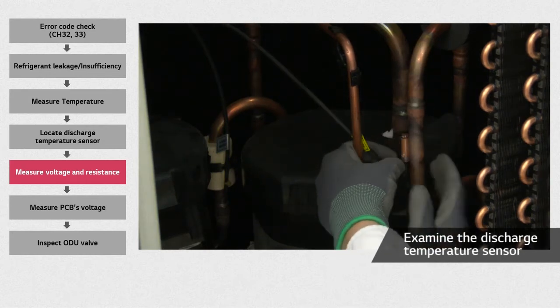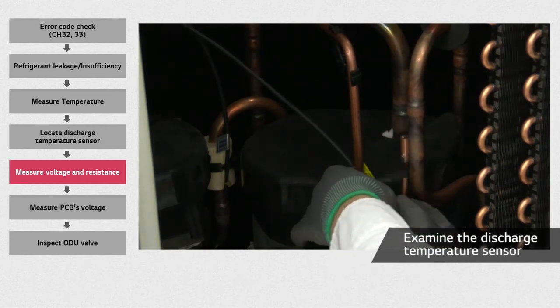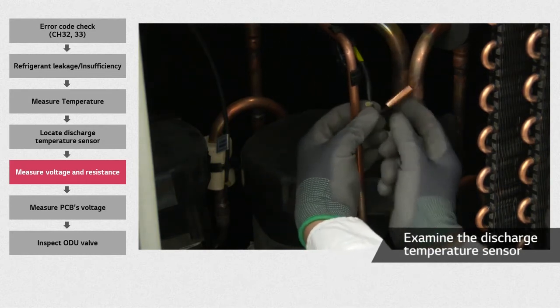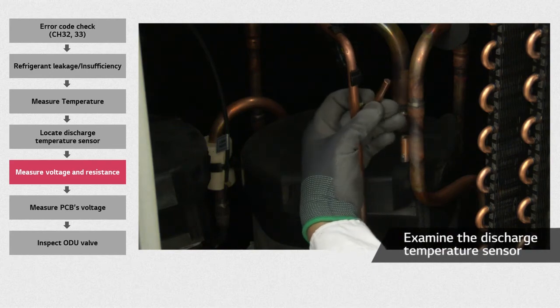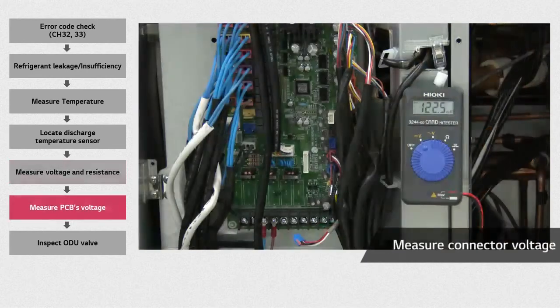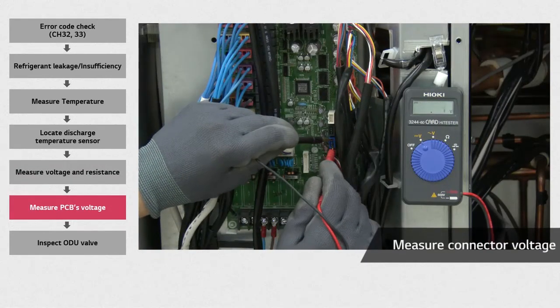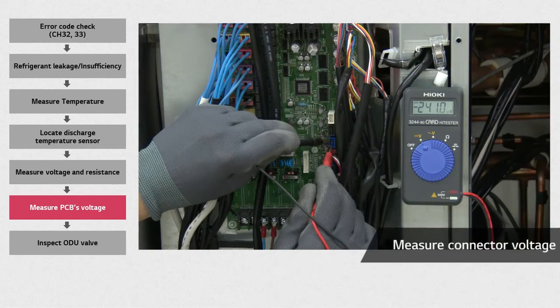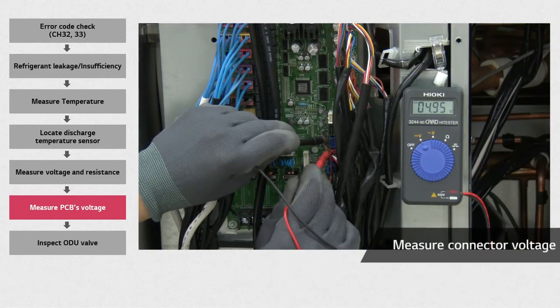To remove the broken sensor, unfasten the clip, remove the insulators and pull them out. Make sure the DC voltage from the external PCB blue connector is 5 volts.